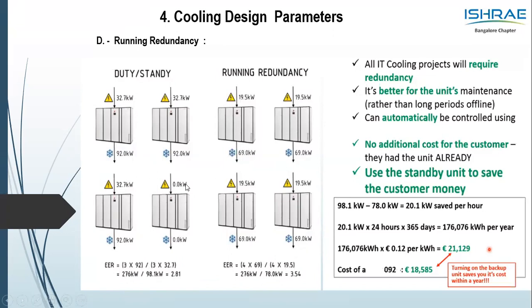Now, the standby should not barely be for a standby. It is recommended to use the standby during the operation. The best bet is to run all 4 units at a bracket of 60 to 70, 75%, because the best energy efficiency from the DX unit is obtained from the bracket of 60 to 75%. So if you run this at, let's say, 75%, the same unit at 75% gives you 69 kilowatt into 4, power consumption being dropped further to 19.5 into 4. You technically get the same cooling capacity, so not to worry on that. But the power consumption running part load at all of these 4 units, there is an increment on the COP. So technically running the fourth unit in this case, or the standby unit, if I have to say, makes more sense in terms of the higher COP or better operational cost.